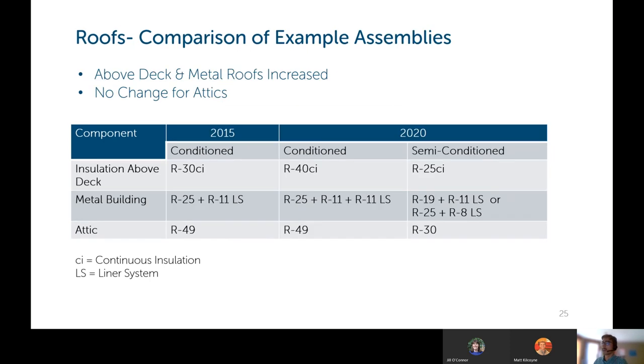Going into this a little more, comparing this to what the 2015 code had, we've got 2015 on the left and the 2020 requirements on the right. There was no change in the attic insulation. You've got R49 for both 2015 and 2020. But then the above deck insulation has increased from R30 continuous to R40 continuous, and a metal building roof has added an extra layer of R11 within the purlins.